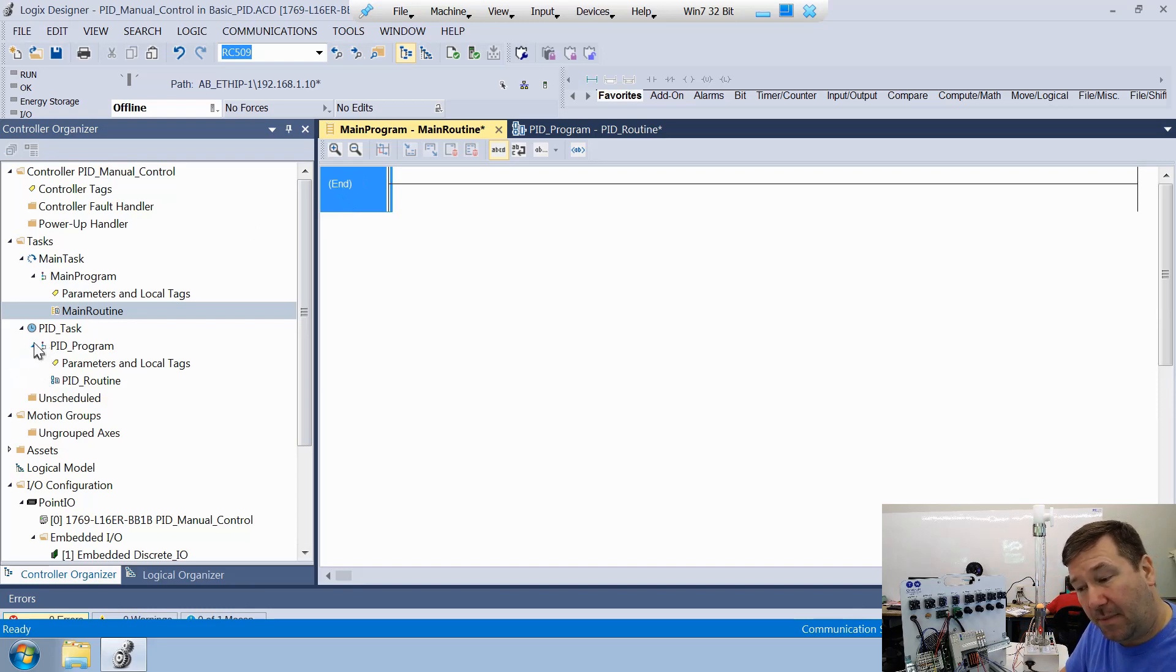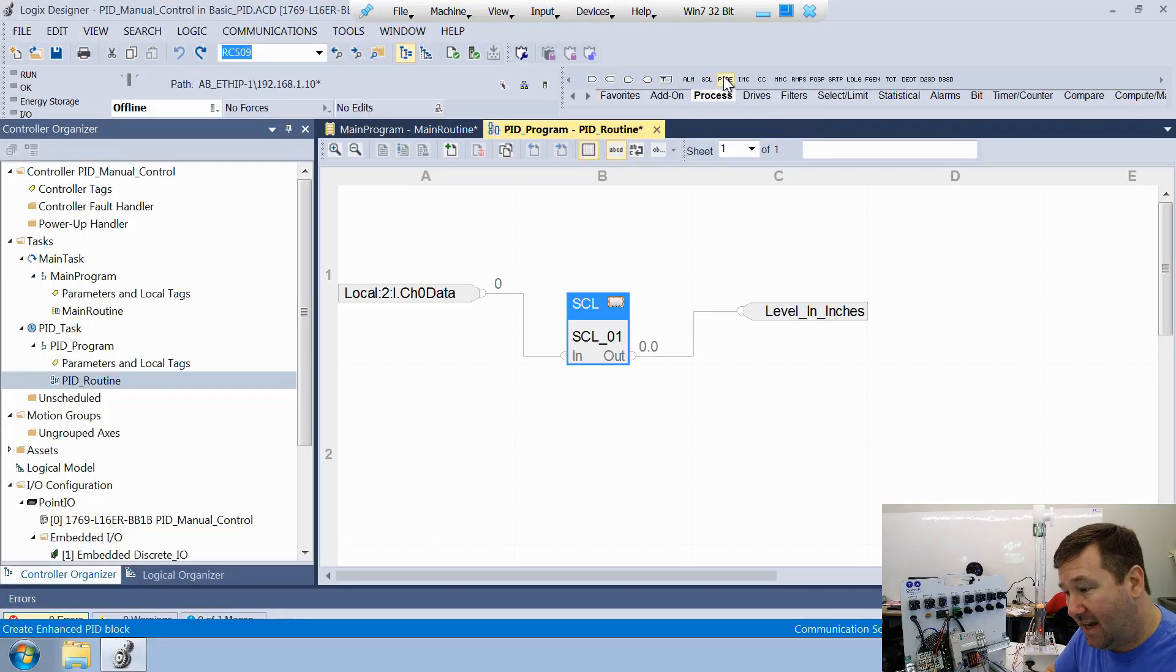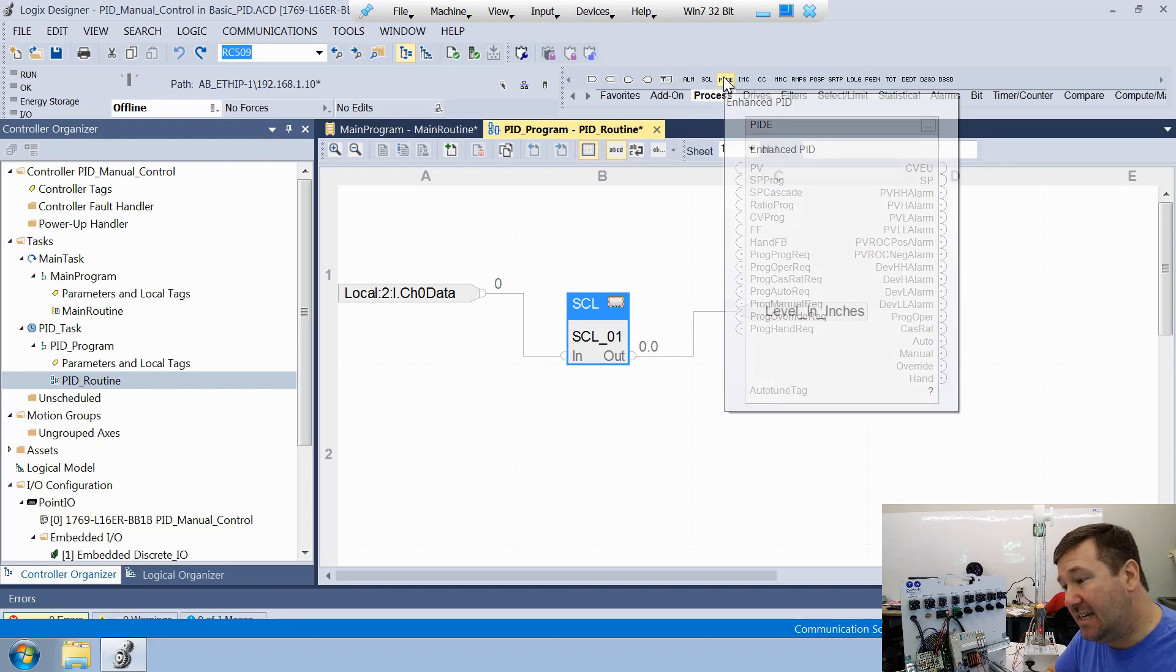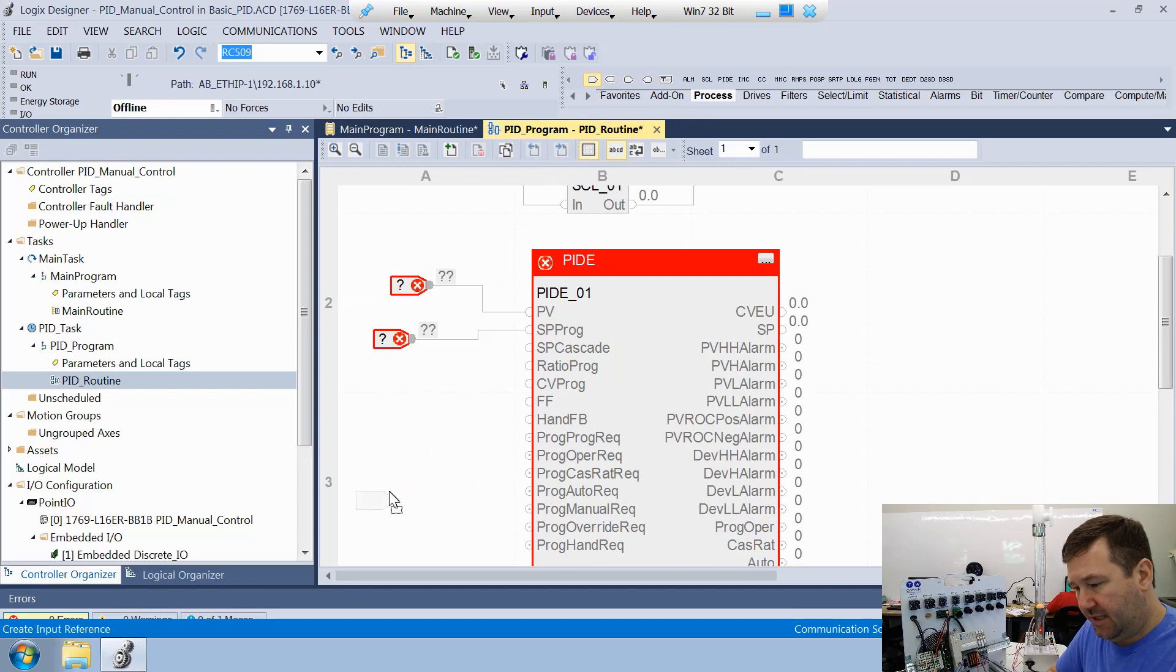And then let's go to our PID task, PID program, and PID routine. And this is where we had done our scaling for our analog input. Now on our process tab, we want to bring down that PIDE instruction, which is our enhanced PID. And then we're going to bring down some of the inputs here. So we're going to bring down an input reference for our process variable, an input reference for our set point variable. And actually for future videos, let's bring one down for our prog prog request and one more down for our prog auto request. And then on our output side, let's bring one down for our CVEU.